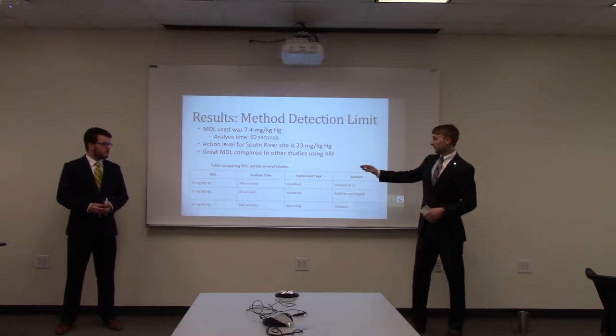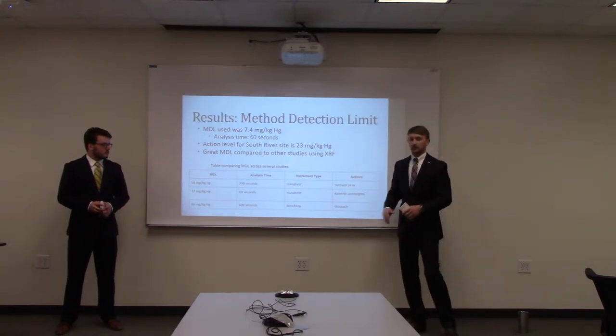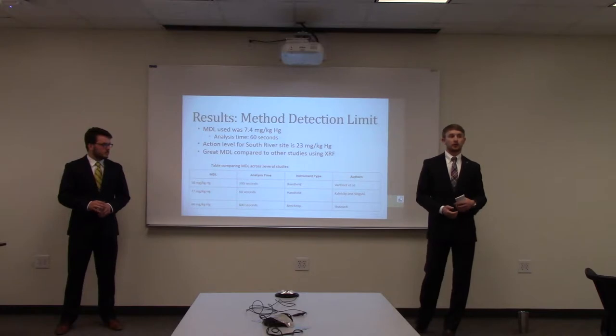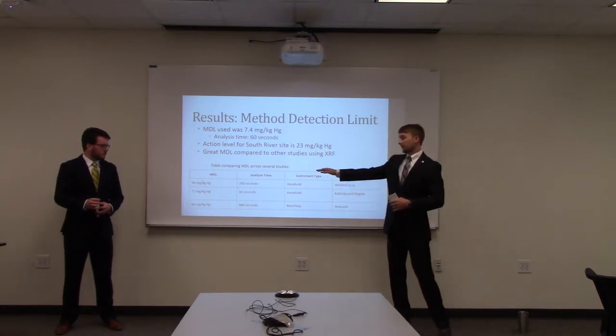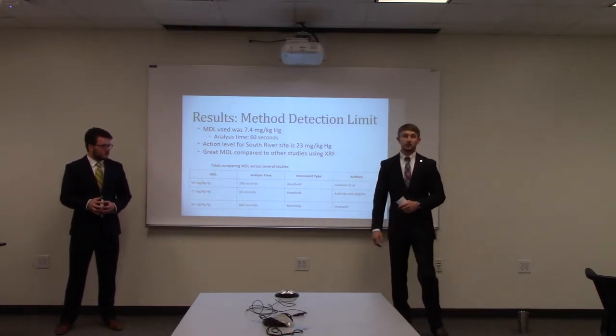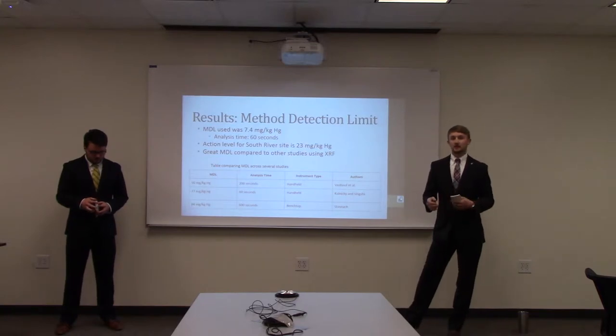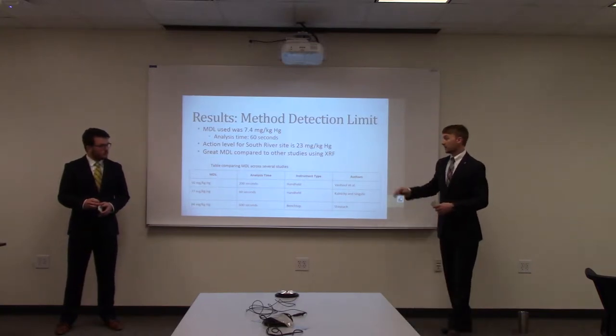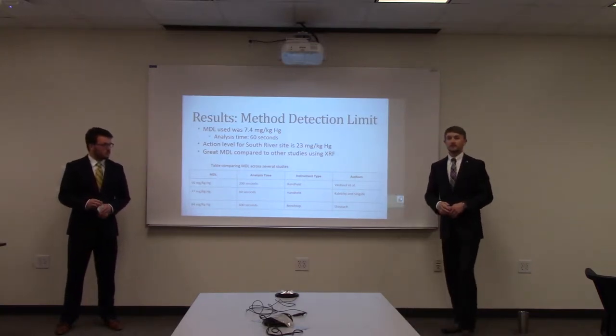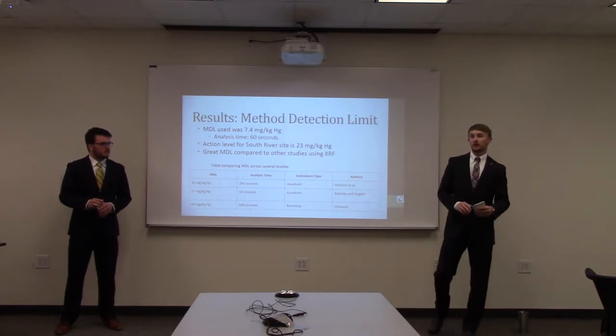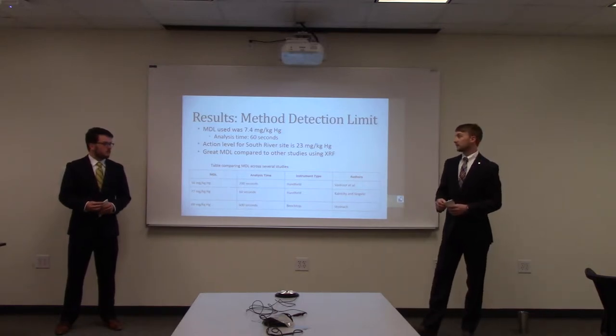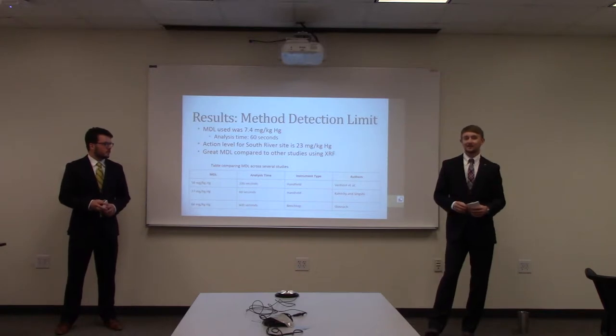Compared to other studies that have used XRF for mercury analysis, we found they really were not lower than 50 milligrams per kilogram, and their analysis times were generally pretty high. So compared to other XRF mercury studies, our method detection limit was significantly lower, with a smaller analysis time of 60 seconds.